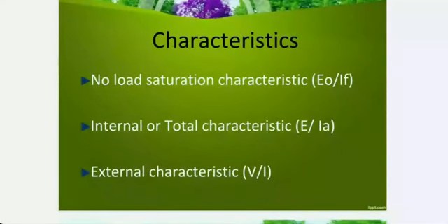So you should know when to stop increasing the field current. Theory apart, the reality also is there. No material can give you infinite amount of flux, no matter how strongly you feed the windings. So this is one characteristic described as the no-load saturation characteristic: the output of the generator connected to no load, simply measuring the total EMF being produced, plotted against the field current going into the field windings.